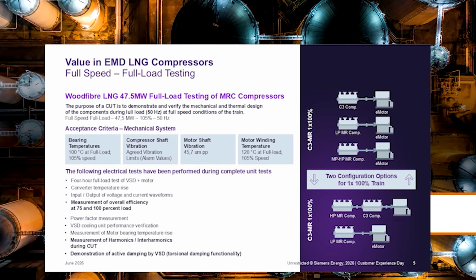We chose LCI type variable speed drives, so that's a current source inverter drive, which normally needs some type of harmonic filter. So that's why we wanted to make sure we were getting the right interharmonics and damping of those harmonic waveforms as part of our risk mitigation testing. So this was all a complete success and shipped to site, so underway on construction there.